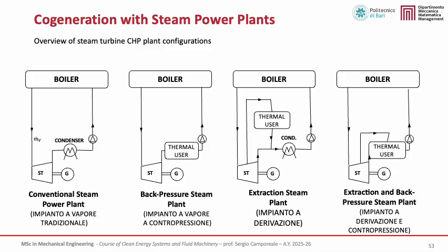The third configuration is the extraction steam plant, in which part of the steam is extracted at an intermediate pressure for the thermal user, while the remaining steam expands further and is condensed. This layout offers greater operational flexibility and could be considered a 2 degrees of freedom system. Finally, the extraction and back pressure steam plant combines both concepts, allowing steam extraction for thermal use and back pressure operation, and therefore providing the highest degree of flexibility among steam-based CHP plants.